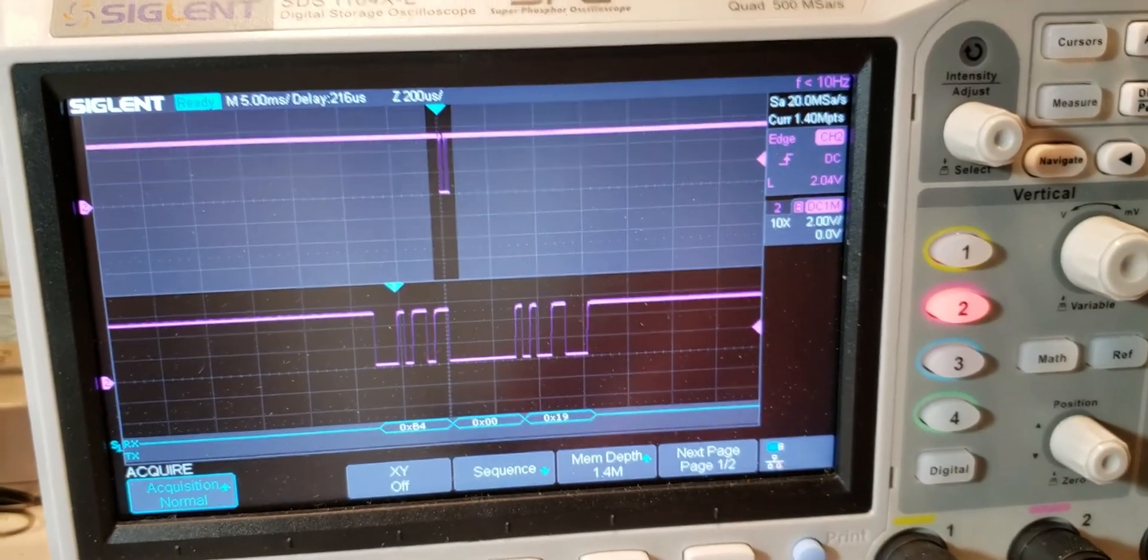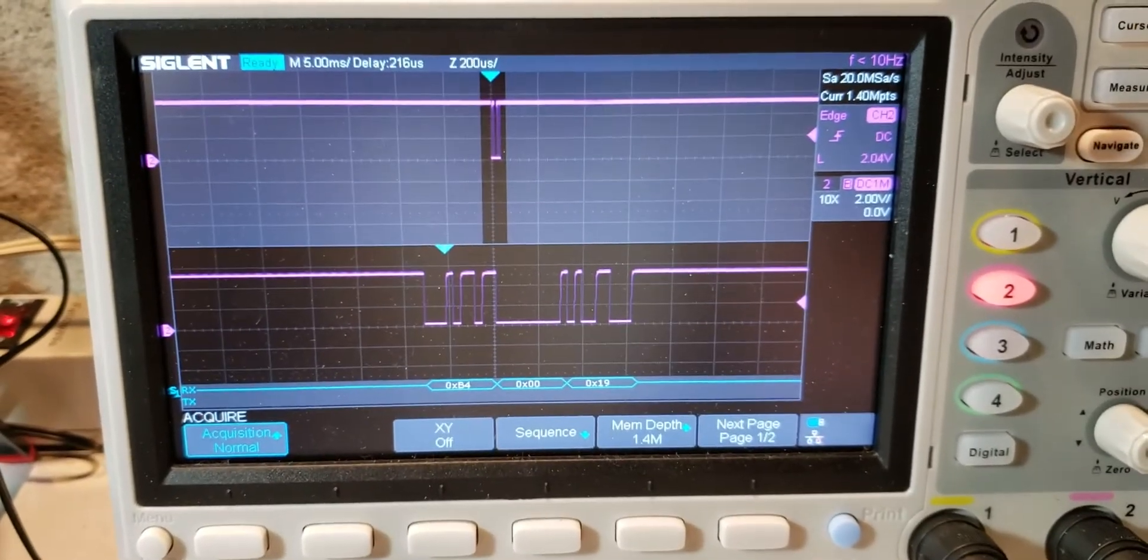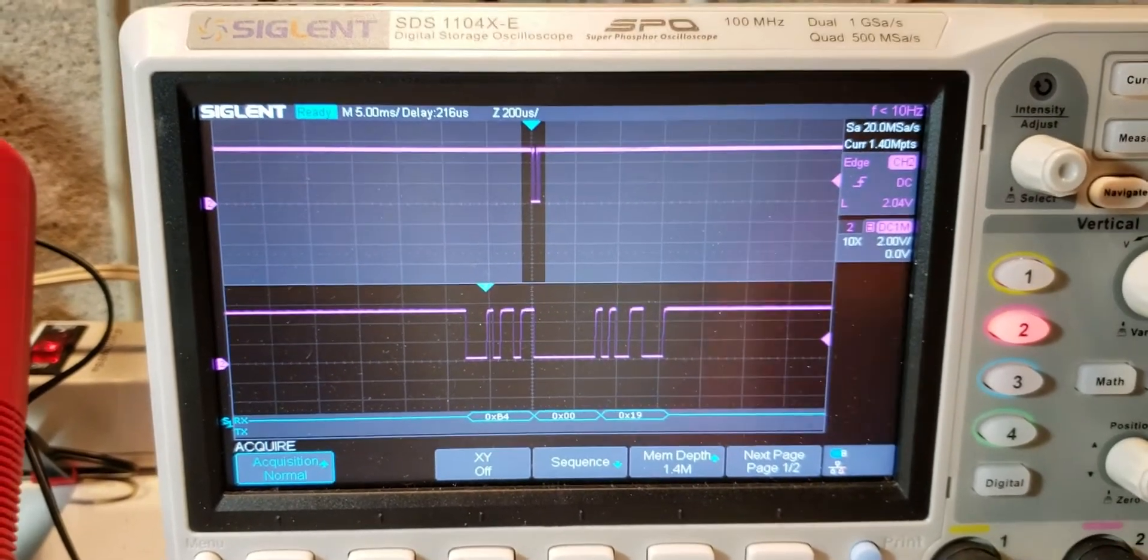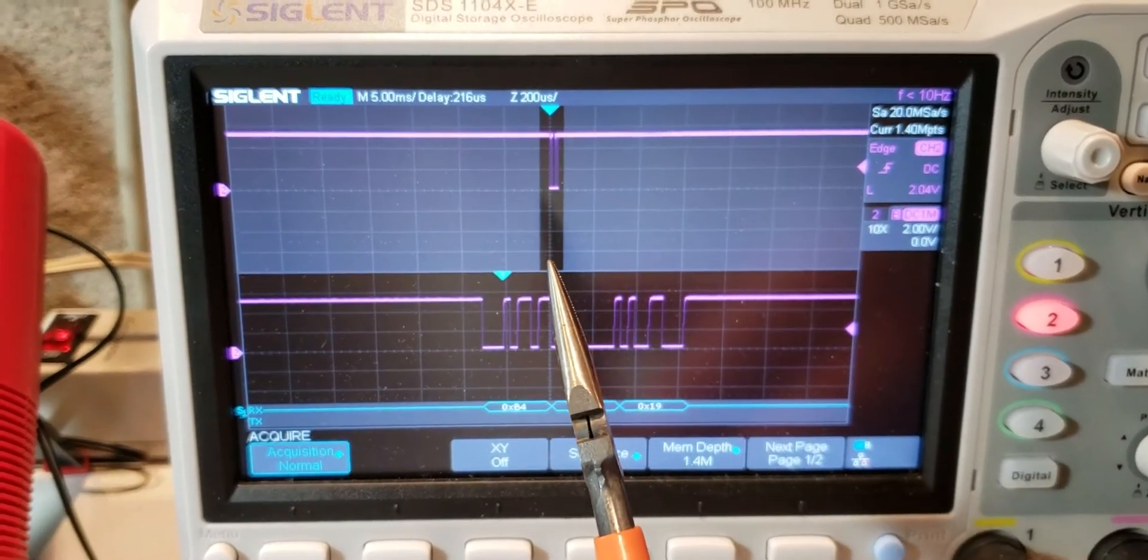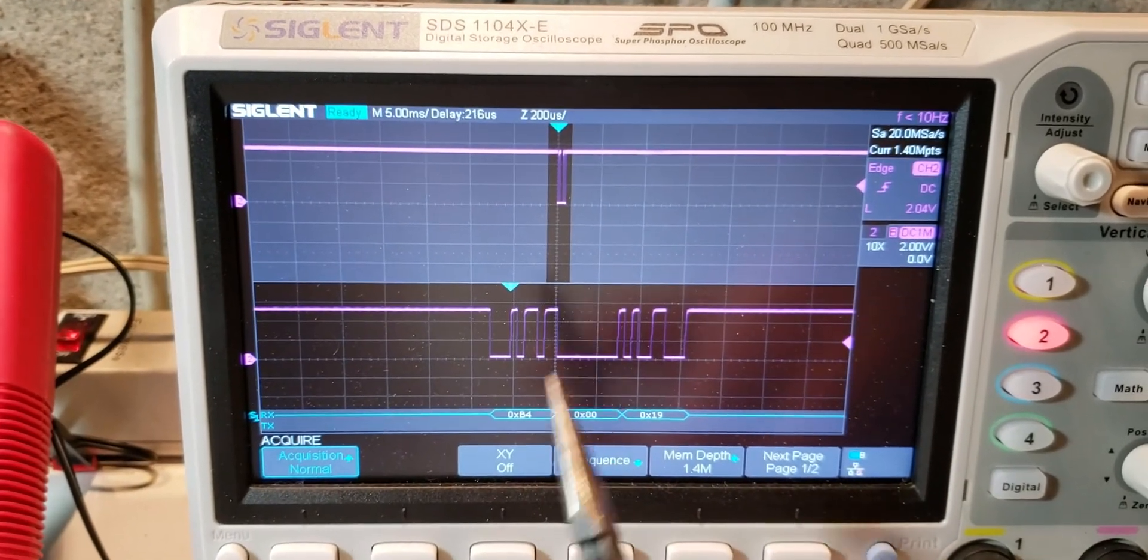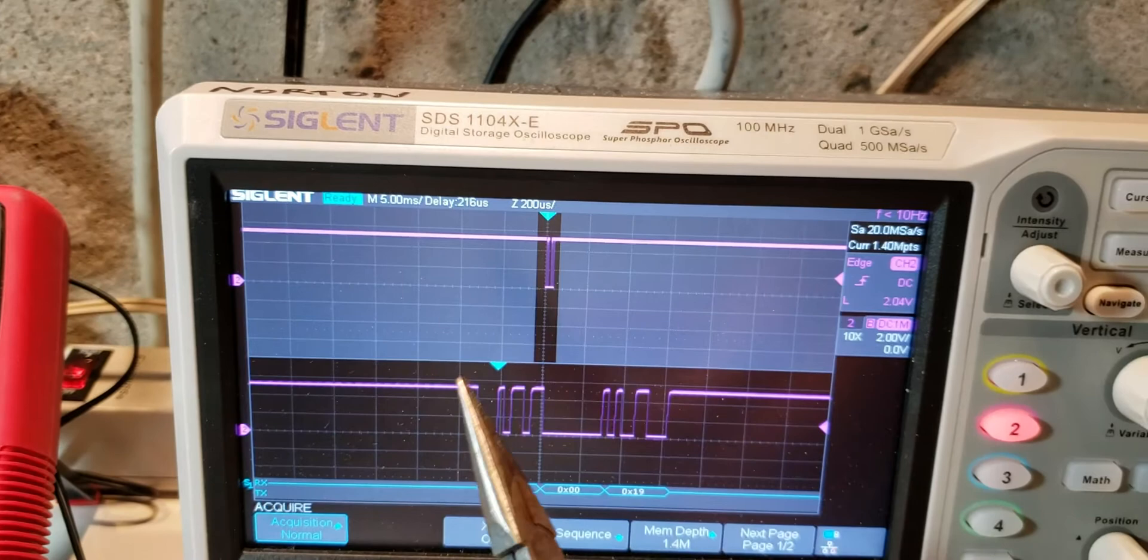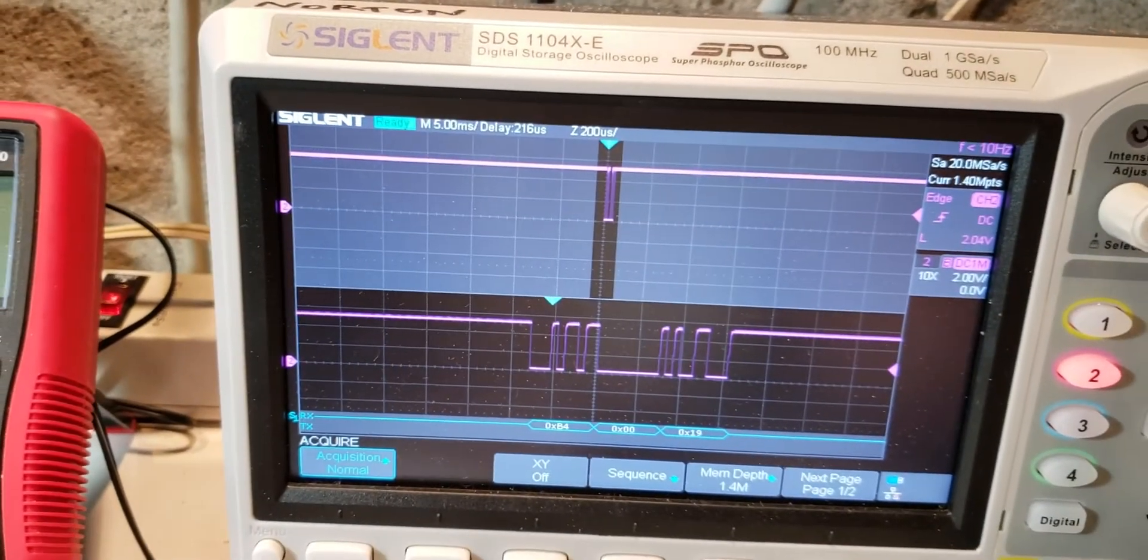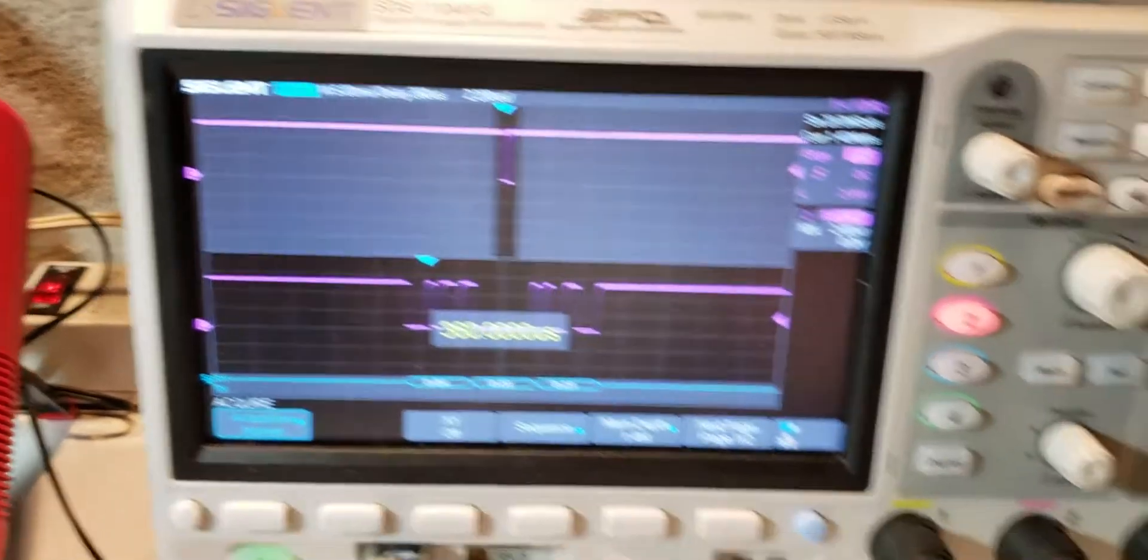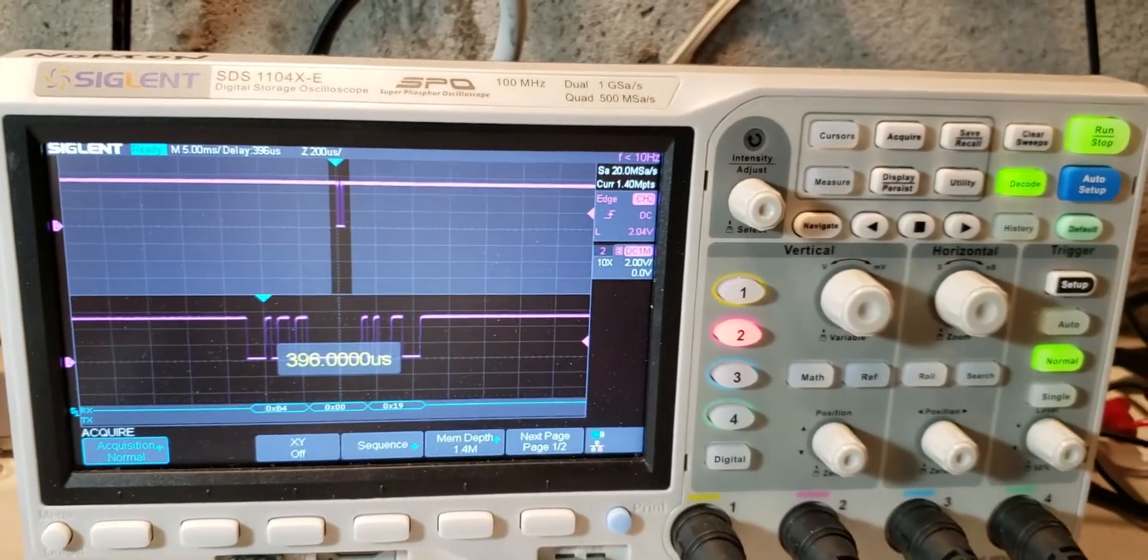So how do you get this set up to do this? And the other really neat thing is you can change the time base. So here there's two time bases. This is the main acquisition up here. This is the expanded acquisition of this region. So you can get a zoom view and decode the zoom, which is really nice because practically you always want to have a wide capture range on the top to see multiple messages. And then allow you to scroll on the main, using the horizontal position here, to, if you have multiple messages, you can look at them one at a time.